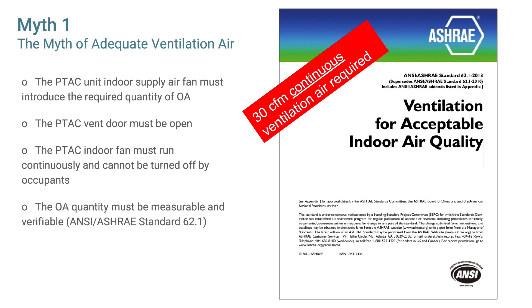For a PTAC unit to perform this ventilation function, several things must happen: the PTAC indoor supply fan must introduce the required quantity of outside air, the PTAC vent door must be open, and the PTAC indoor fan must run continuously. This is often a problem because occupants control the PTAC units and will either turn off the fan or reduce the fan speed.